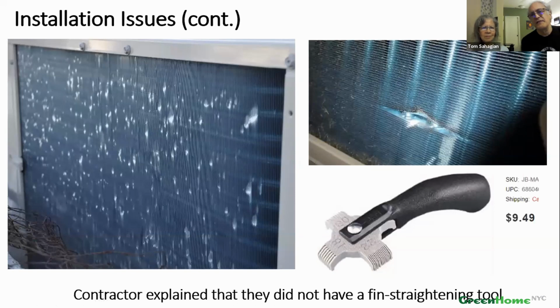We also found little things here and there. It's not a big deal, but you see these crushed fins on the outdoor unit heat exchangers, and you really shouldn't have too much of that. These ones here, there are a lot of them. They're small, but they add up to something. And this one here is actually kind of serious looking. We asked the contractor to get a fin straightener and straighten these out, and they said, well, we don't have one.